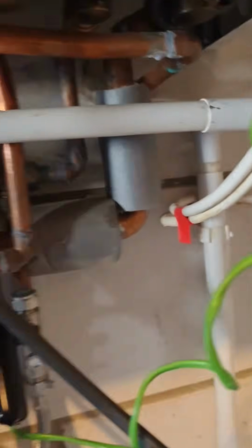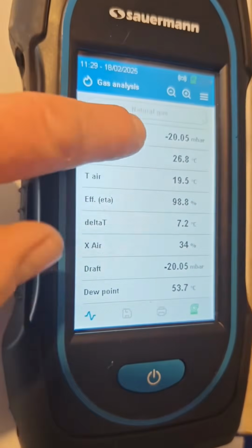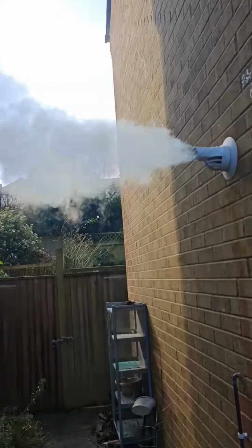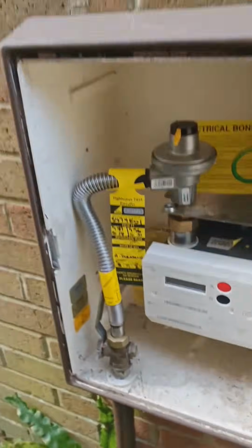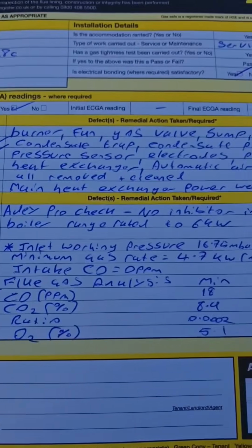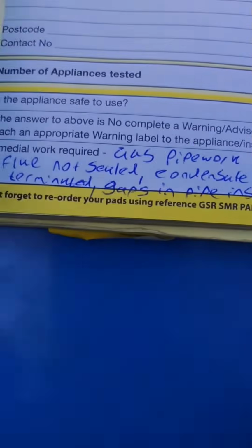So I'm using my test equipment now just to test the various pressures, temperatures and the flue gas, which I can use my analyzer to check everything is correct and if anything needs adjusting. From here to do our tests at the gas meter. Work is being filmed, the work I've carried out and our findings.